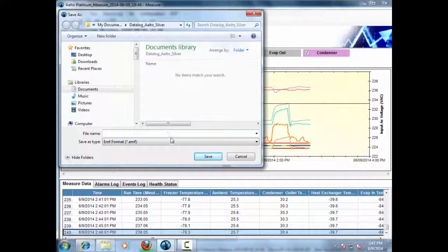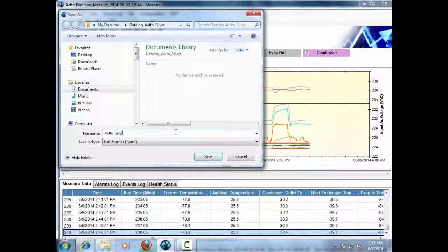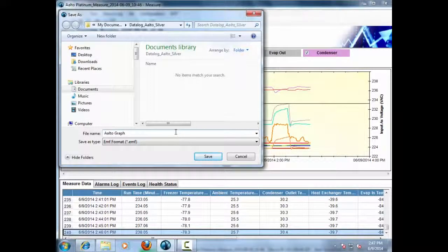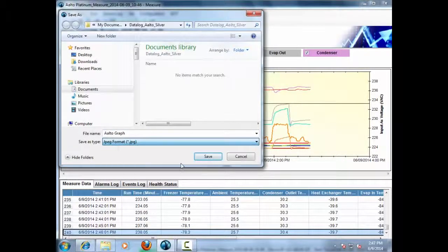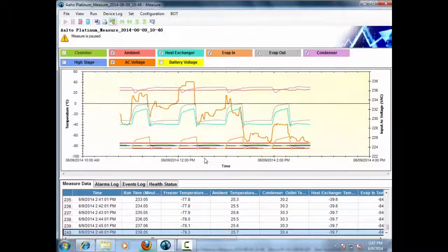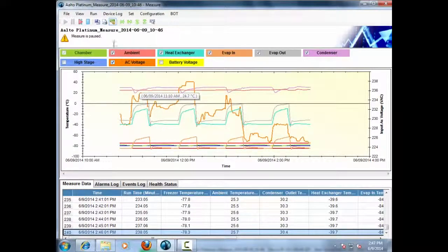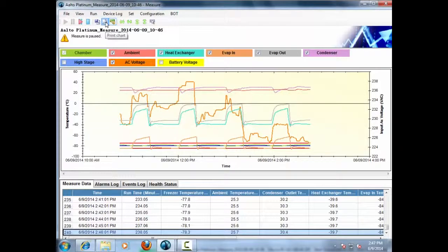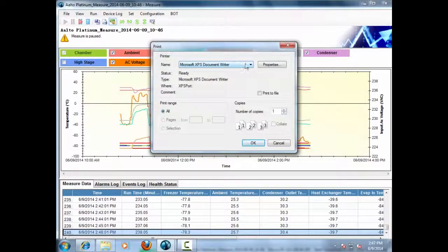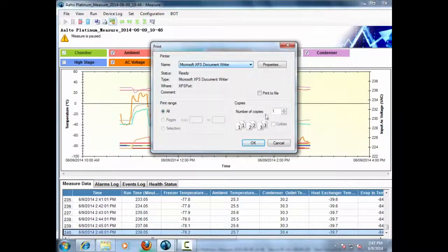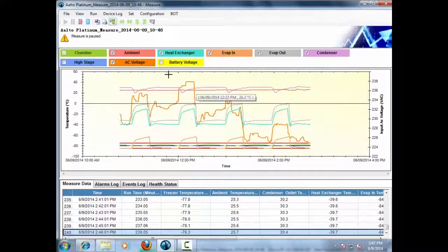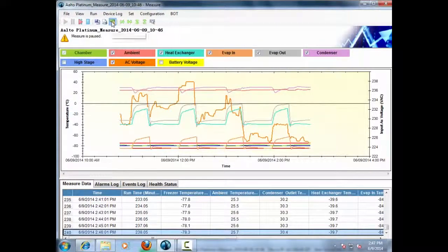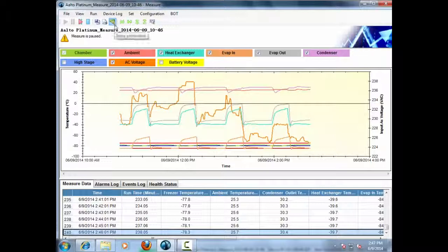On the measurement screen, different menus can also be accessed, such as File, View, Run, and Device Log to read freezer temperature log, sensor logs, event logs, battery logs, and SMS logs. Set, wherein users can set temperature setpoint and high and low temperature alarm setpoints.